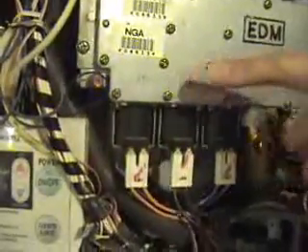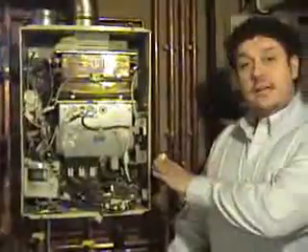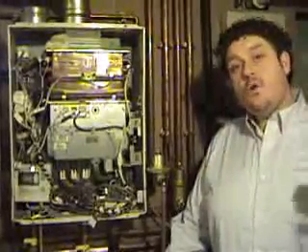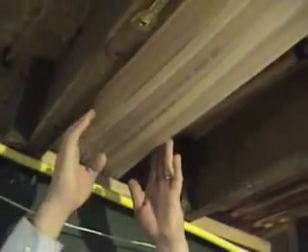This tankless water heater provides us with a very small margin of error. The incoming water temperature is calculated internally with this computer strip, which allows us to determine exactly how much gas is needed to raise the water temperature up to our heating needs. The water comes out of the unit at its design temperature, then travels into this balanced loop manifold, which distributes the heat evenly to each zone. From the zones, the water travels to the subfloor. I installed these pipes to the underside of the floor, which consists of half-inch PEX heating pipe with a 60% glycol mix. On this side of the joists, we can see that I have grouped this distribution network for the zone, which then leads up to my second floor heat distribution system.